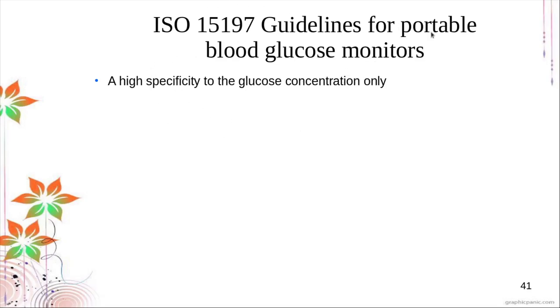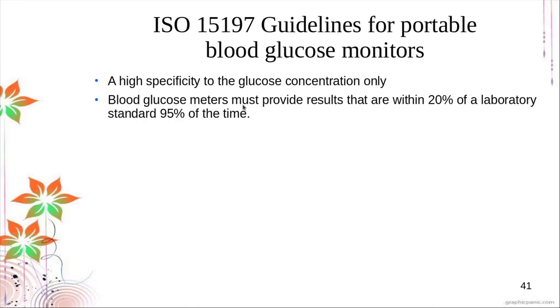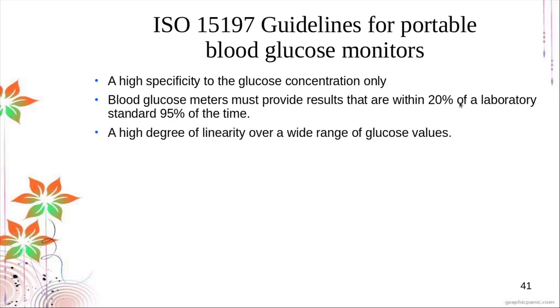The requirements for a portable glucose monitor under ISO 15197 include: high specificity to glucose concentration only, with no cross-reactions with other blood sugars or non-sugars such as salicylic acid, aspirin, or maintenance drugs. Blood glucose meters must provide results within 20% of the laboratory standard 95% of the time — meaning both accurate within 20% and precise 95% of the time.